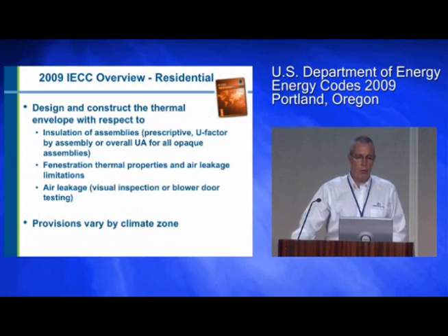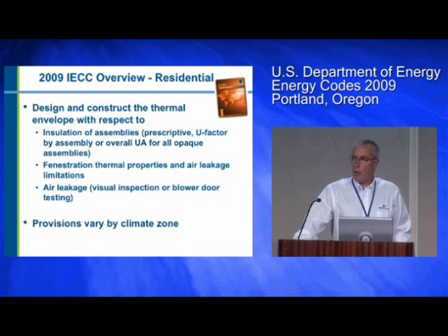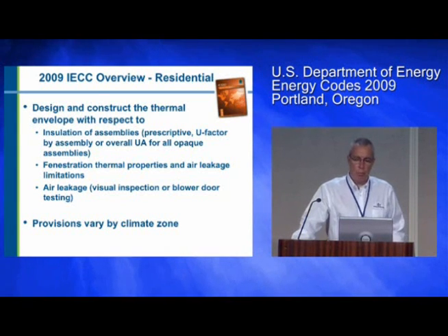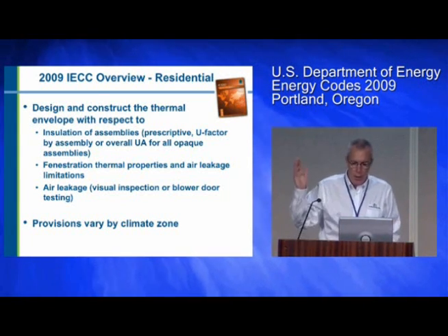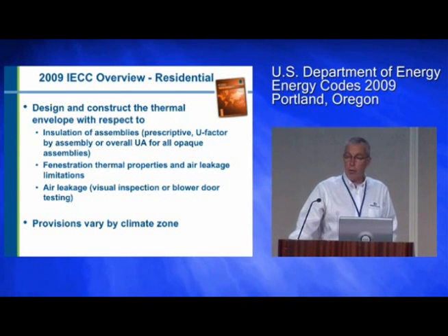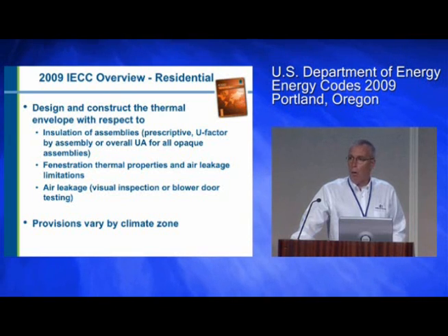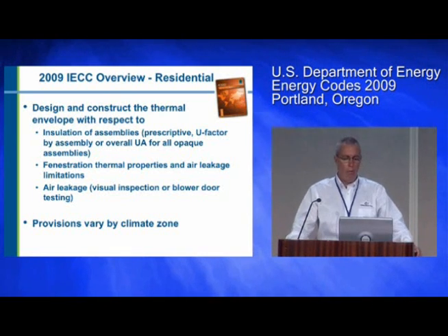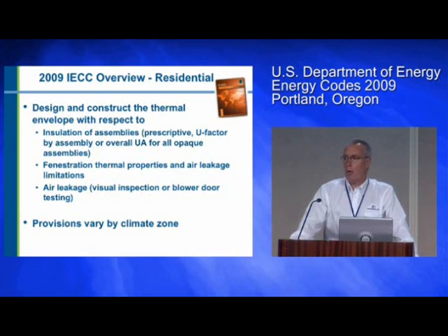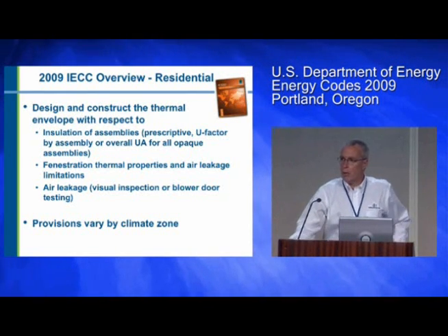There are 8 climate zones in the U.S. You have to design and construct the thermal envelope with respect to insulation. There are a couple of paths to compliance: prescriptive, R38, R19, R13, what have you; U factors by assembly, the opaque wall U value of X, or an overall UA for all opaque walls. Put a little bit more in the ceiling and a little less in the walls, and you can show compliance. There are provisions for fenestration, thermal properties, and air leakage. If you've traced these over the years, you would see that what they used to call U values, now U factors, have come down significantly.